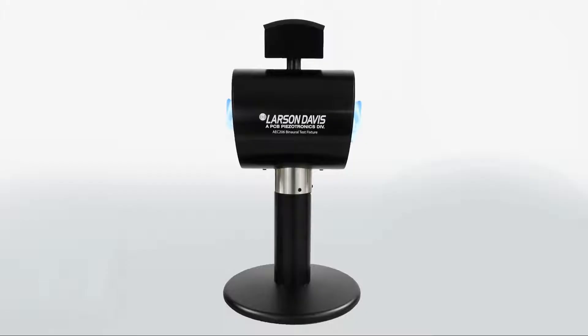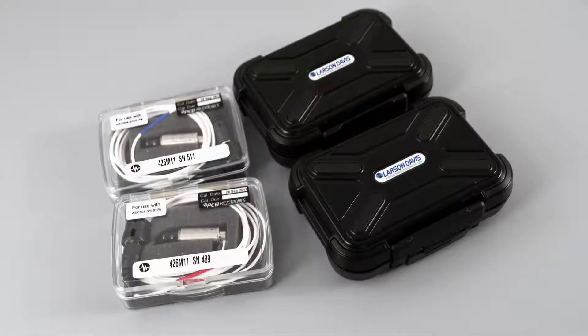This video is not for assembling a newly purchased AEC-206, as it will come pre-assembled. This video will walk you through assembling the occluded ear simulators and preamps that you may have sent in for factory calibration. Once the AEC-304 occluded ear simulators and 426M11 preamplifiers have returned, you are ready to reassemble.